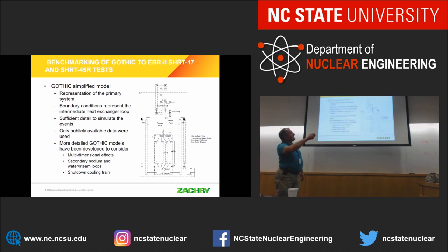So as I said, this model was driven by boundary conditions on the secondary side. There was a benchmark specification provided by ANL to others that wanted to simulate the transients, and the boundary condition information was available when we used that. It allowed us to keep the model small and simple and be able to run the test. We also have additional models that have additional detail in them, much higher detail in the core region, much higher detail in the pool region, more multidimensional than we used for this simple benchmark. We've also modeled all the way out to including the intermediate heat exchanger system, steam system, including the steam generators, which now is water and sodium. And finally, we have a model that has the shutdown cooling system rejecting heat to the environment through the air stack.